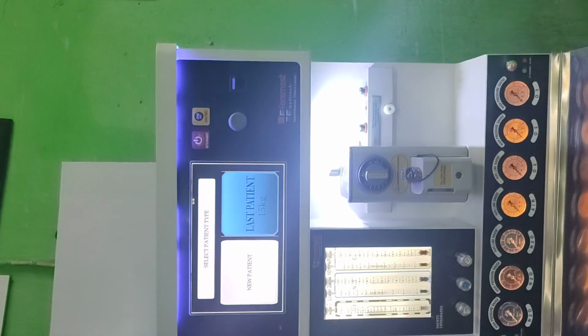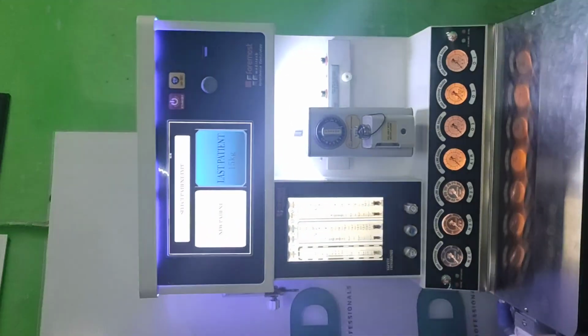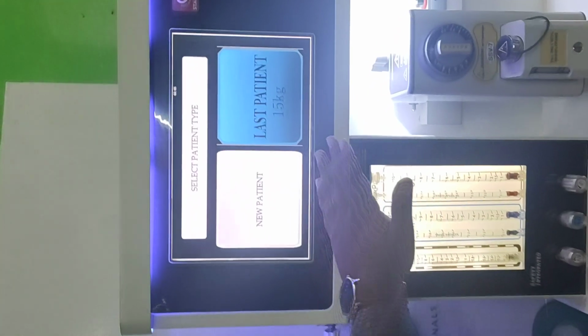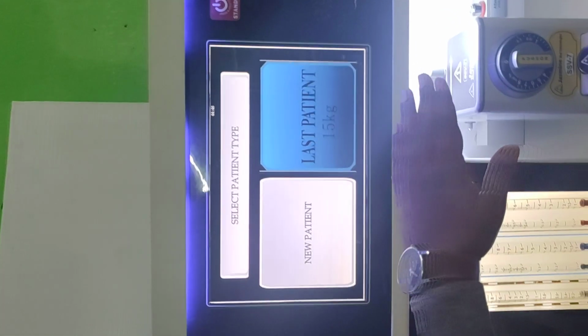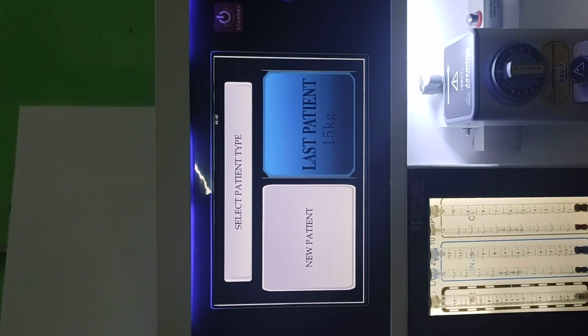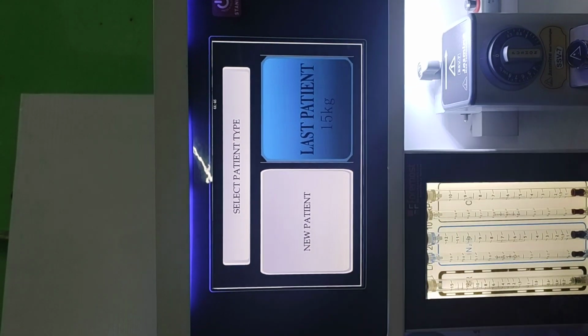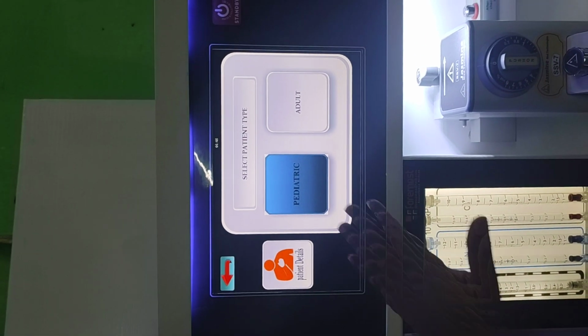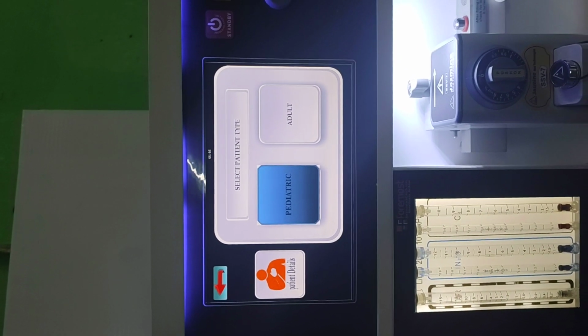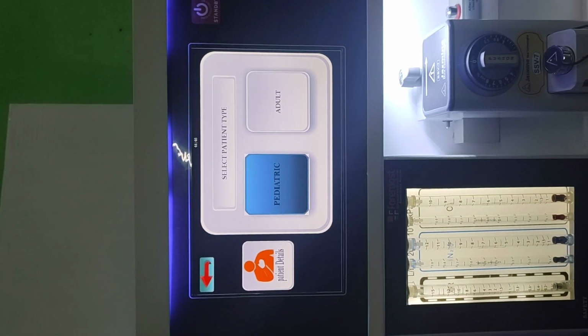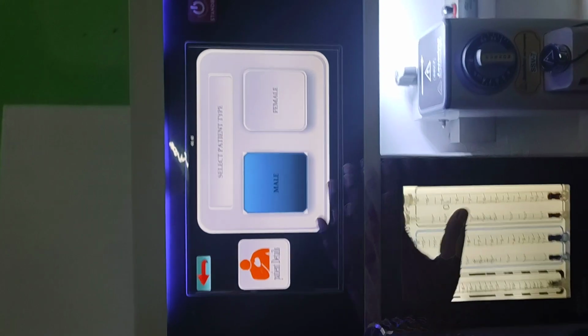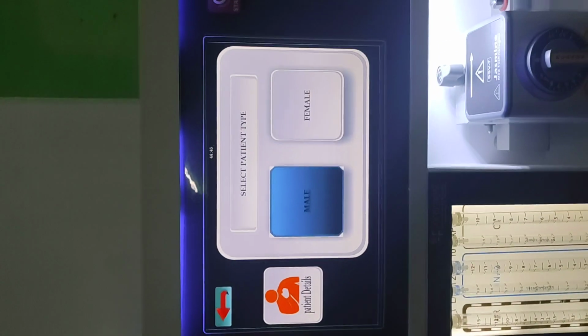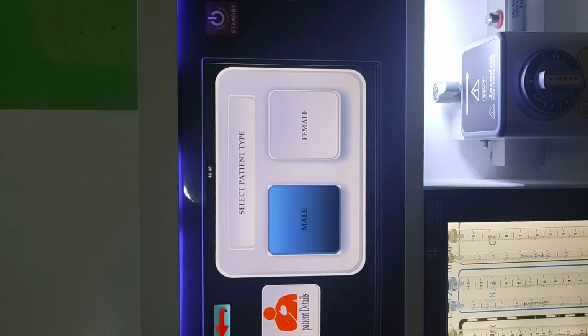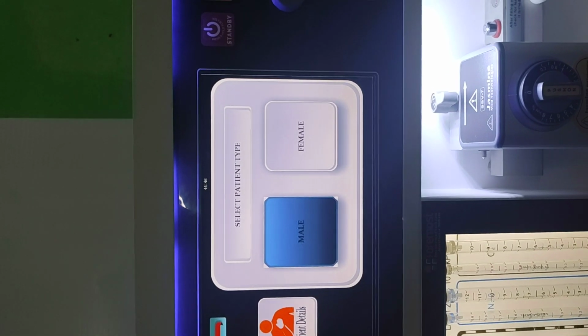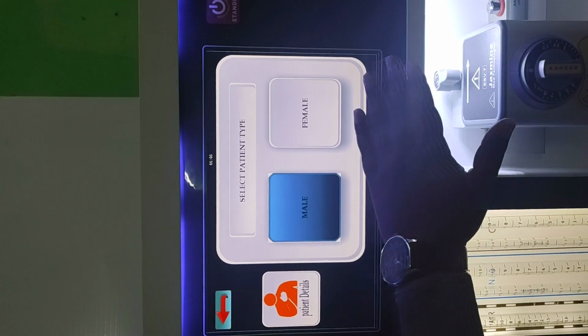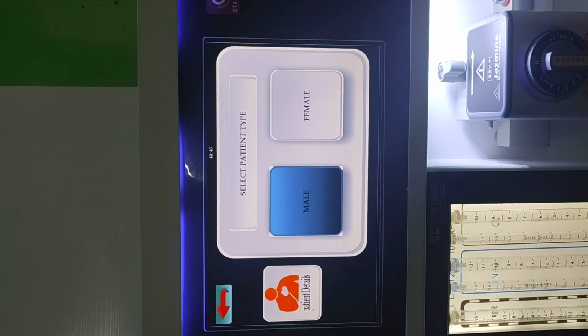This is a 12-inch full touch display, and the first screen prompts you to select the patient type: last patient or new patient. If you are ventilating the same patient again, you can choose the last patient, or you can go for a new patient. In new patient, both pediatric and adult selection is there, so the machine can be used for both adult and pediatric purposes. In adult, you also have the choice of male and female, because it sets the default parameters. If it's male, it will set the default male values. If you select female, it will set the parameters as per the female default values.